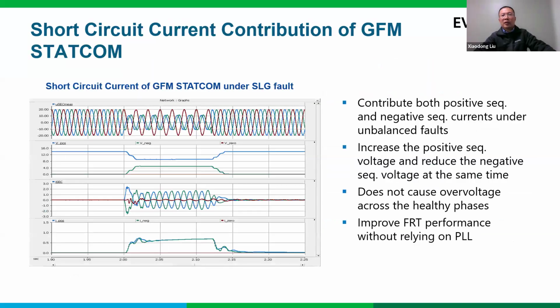All right. So what about the STATCOM performance during a fault? That is the short circuit contribution of the grid forming STATCOM. This question is important for protection. From the example here, a 7-cycle single-line ground fault, you can find that the grid forming STATCOM contributes a good amount of negative sequence current. It's good for protection.